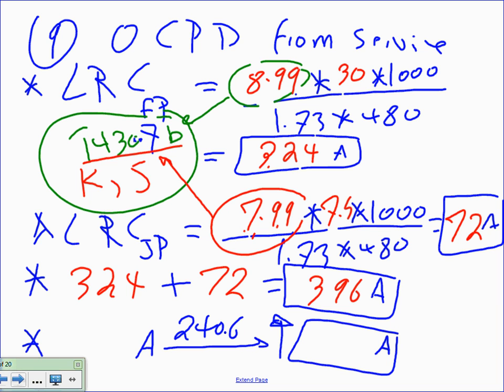And if you take the 396 amps, take it to 240.6 and go up because these are non-adjustable. We're using a non-adjustable circuit breaker on it, so 240.6(A). If it's adjustable, Chris, a circuit breaker can go as low as 396 if I can adjust it. We're using non-adjustable on it because it's cheaper, so that will go up to which standard size? 400 amp. So the overcurrent protection device is going to be a 400 amp.